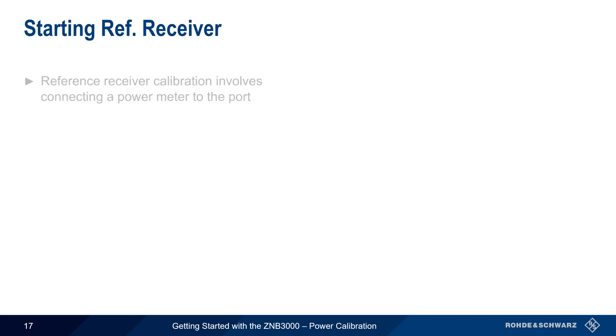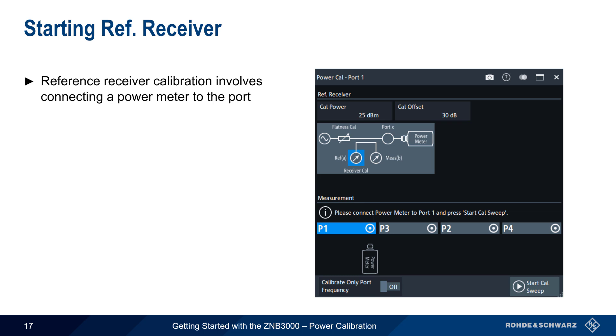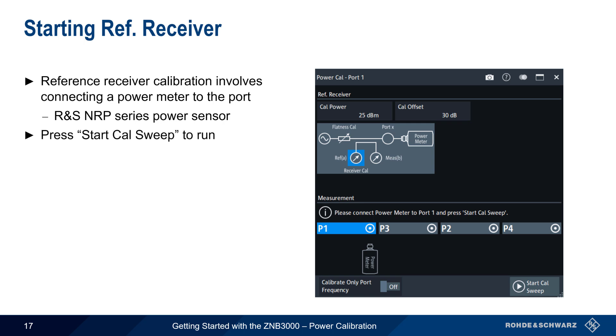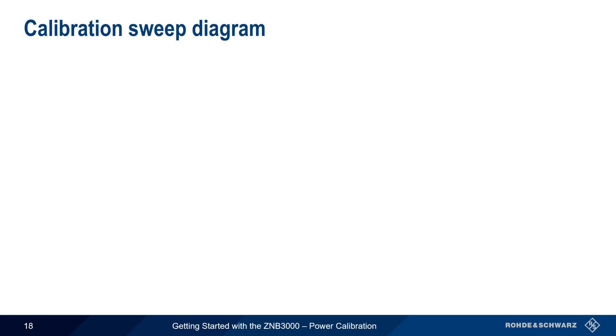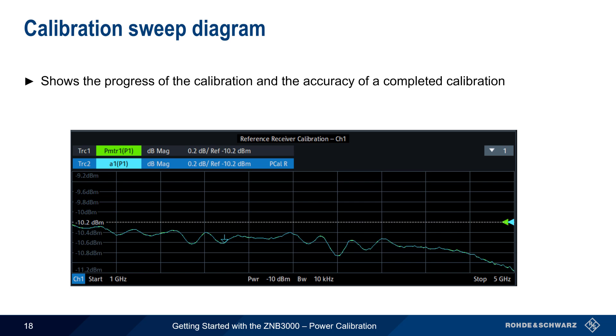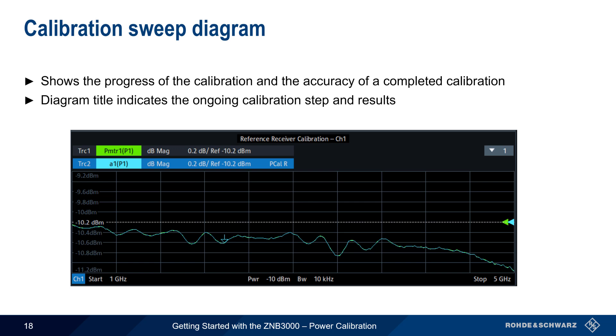Reference receiver calibration involves connecting a power meter to the port being calibrated — generally a Rohde & Schwarz NRP Series RF power sensor. Once the sensor is connected, press Start Cal Sweep to run the calibration, which only takes a few seconds. At the top of the power calibration window, a calibration sweep diagram shows the progress and accuracy of the completed calibration. These diagrams are available for other steps as well, with the title indicating the current calibration step and measured results.